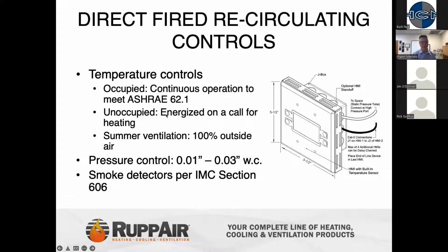Direct fire controls. When you get to the temperature controls, you're going to have occupied and unoccupied capabilities. And the most important thing within these recirc style units is make sure you have controls that can give you this control and this flexibility. Occupied mode is continually operating to meet those ventilation requirements. Unoccupied can be energized on call for heat only. But then also third, having the ability to have this equipment operate in that summertime ventilation mode of 100% outside air. So a lot of flexibility from continuous heating mode to cycled unoccupied mode to high volumes of fresh air for summer mode.